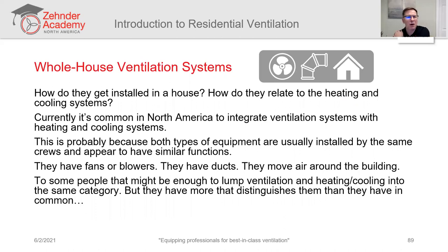Okay, so let's talk about whole house ventilation systems. Basically what we just covered was sort of one advanced feature, which is actually incorporating energy recovery. By the way, those BTUs that we talked about being lost if you don't do energy recovery, a good energy recovery system can recover, let's say 80, maybe even 90% in some cases of that lost energy. So that's a big deal. That's a worthwhile investment for something that's going to be running for the next dozens of years.